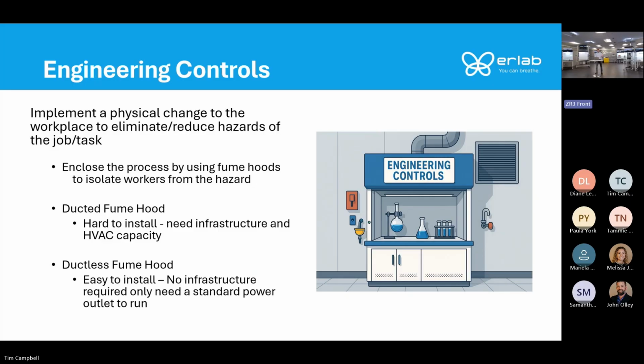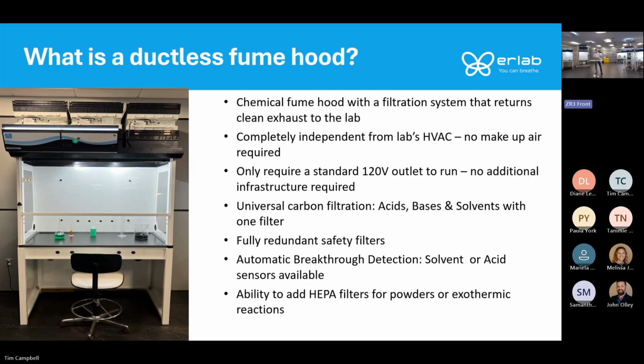So what exactly is a ductless fume hood? For those of you who don't know, it's that same chemical fume hood that you're used to using, that traditional one. But instead of having that ductwork, they're using an advanced carbon filtration system to capture the chemical vapors and fumes that are generated within the enclosure, and it returns clean air to the lab. It's not part of the HVAC system, so it's very easy to add. You don't need the infrastructure. You don't need to rebalance the lab air. You just need a standard power outlet to plug it in.